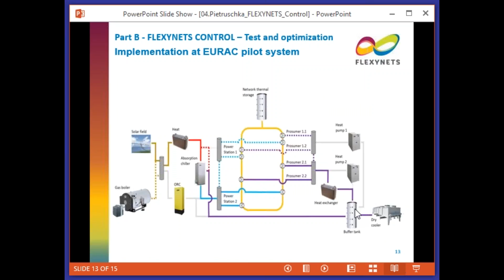To conclude shortly, I'm nearly through. We have one demonstration site in Bolzano where we test all these control issues in a laboratory test system with a solar collector and gas boiler as heat sources. We have absorption chillers and ORC units within the system, and a simulated network where different prosumer substations can be connected and controlled, so we can really simulate a real network, with different operation modes from heating to cooling and distribution. Here you see some pictures of this demonstration site in Bolzano, which is already in operation, and we can now start testing the different control strategies at the laboratory level.